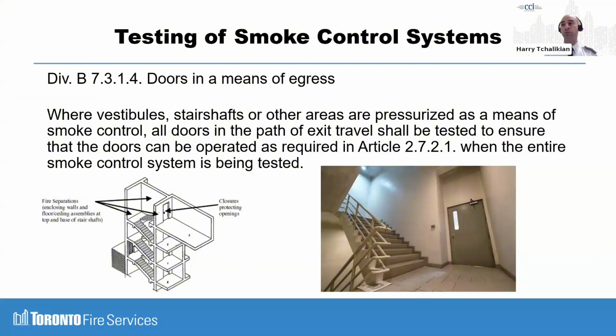If you have issues with regards to pressure changes outside to inside, that is a matter to be resolved by HVAC, heating, ventilation, air conditioning. Do not cut vents into your door, obviously. You just have to be able to balance the pressure such that these doors always open with not more than 90 newtons. We can talk about more of that later.